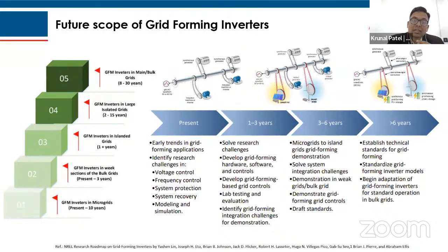If you look, there are three stages of this representation of a mechanical shaft, where motors or synchronous generators are connected to a common shaft through weak links, and the loads are connected with weak links. But when smart PV and wind are connected with the help of grid forming inverters, it becomes a strong link connection with the mechanical shaft of the overall scenario. Further in the future, along with PV plus battery and wind plus battery, this becomes a solid scenario, where you can observe no weak link in the shaft, and this becomes a perfect microgrid scenario in the future.